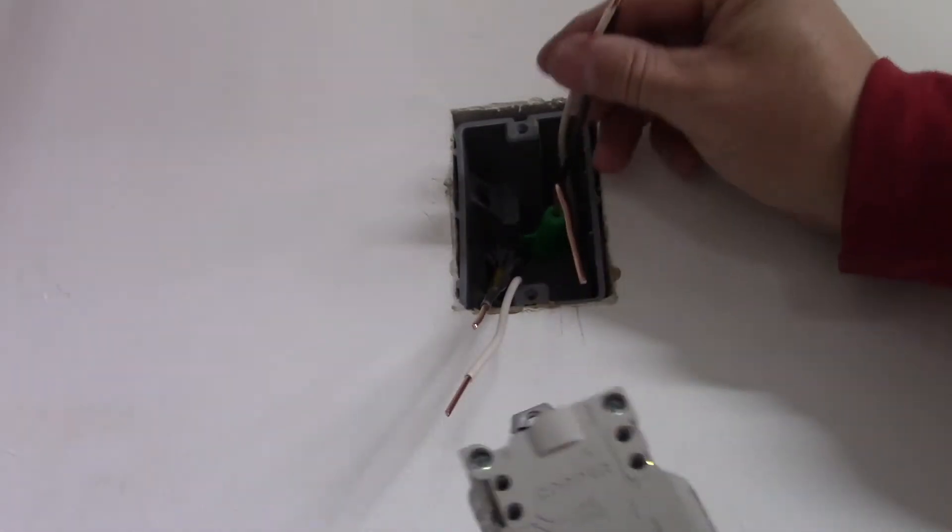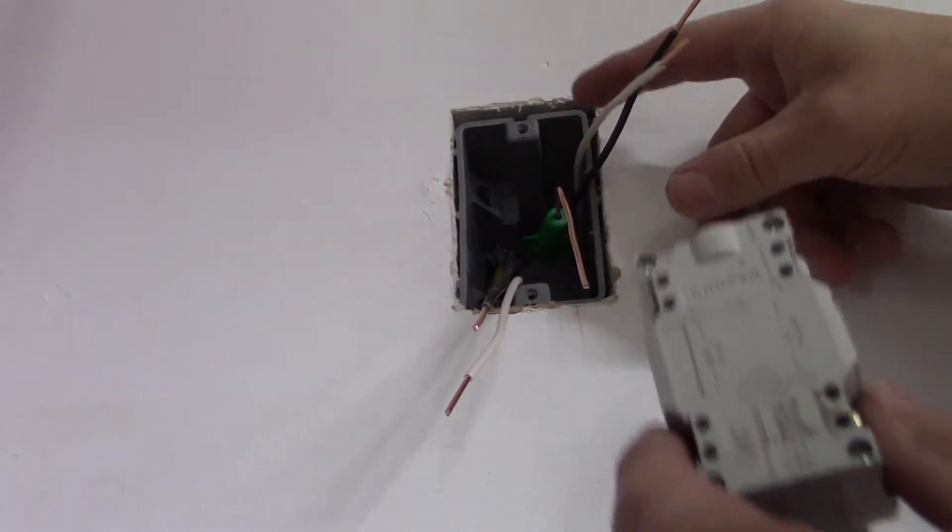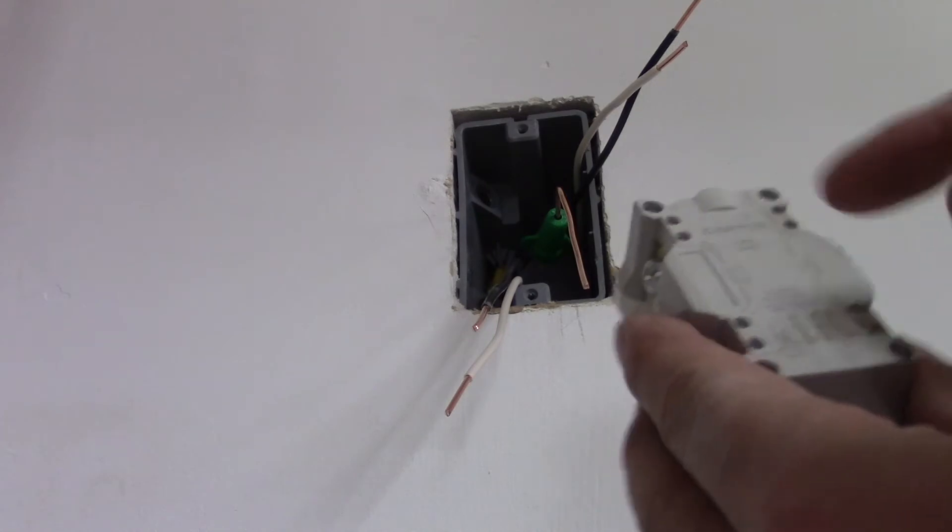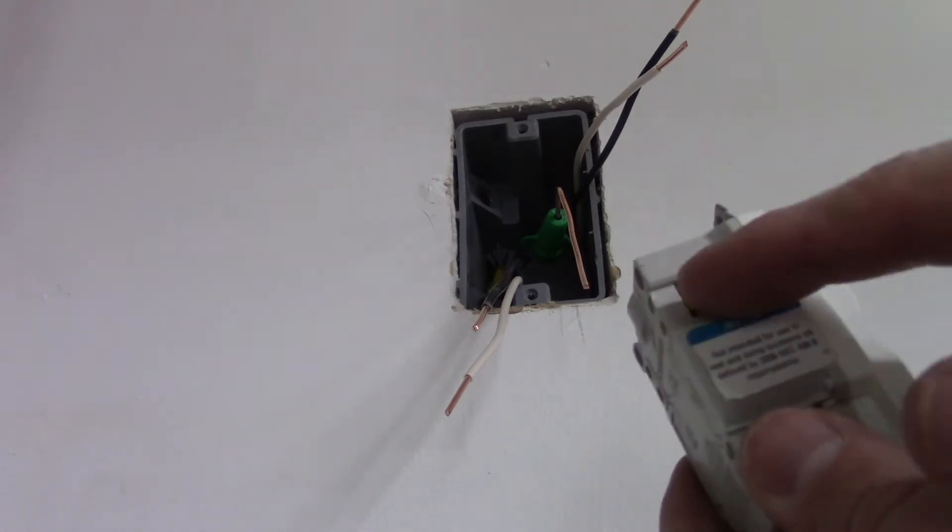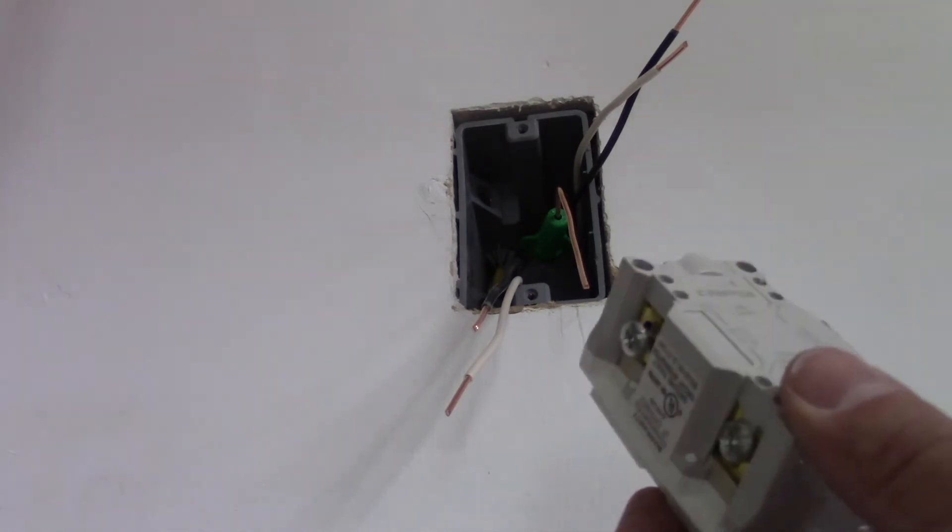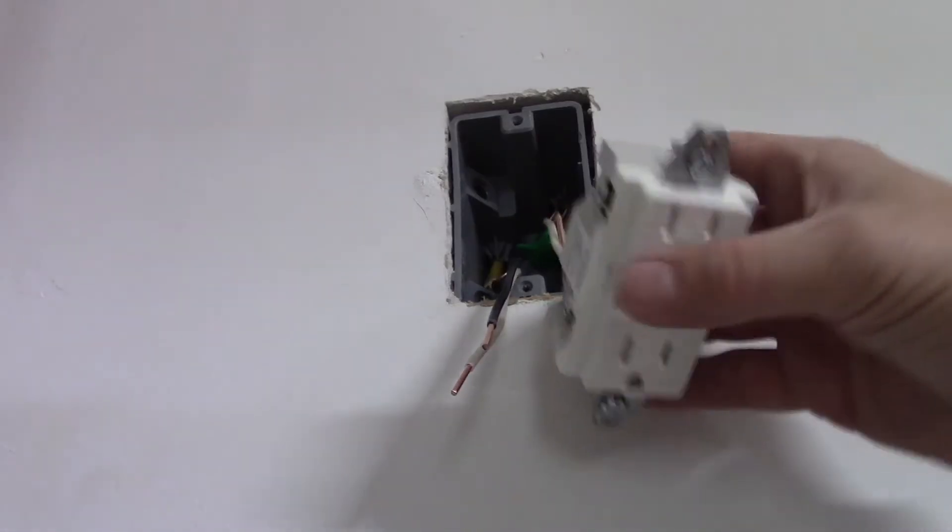The ground wire is going to slide right along this channel and go behind this metal plate here. And when I tighten the green screw, that's going to hold the ground wire. I'm going to take these two wires on this side that are coming from the panel and hook them up to the line at the top of the outlet. The black wire is going to go to the gold terminal and the white wire is going to go to the silver terminal. Okay, so now my line side is connected.